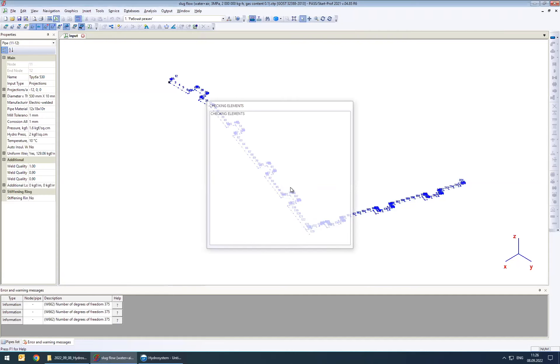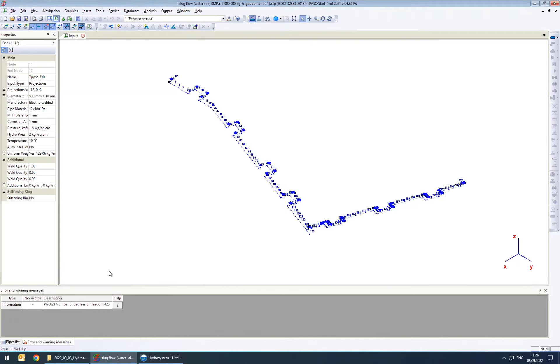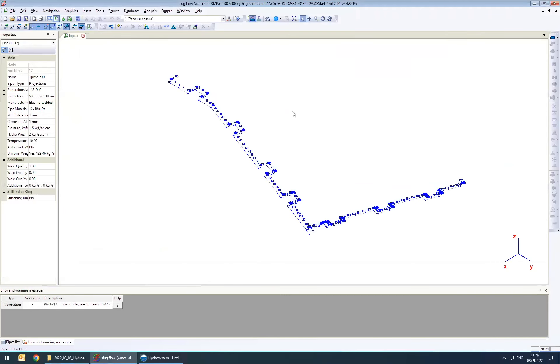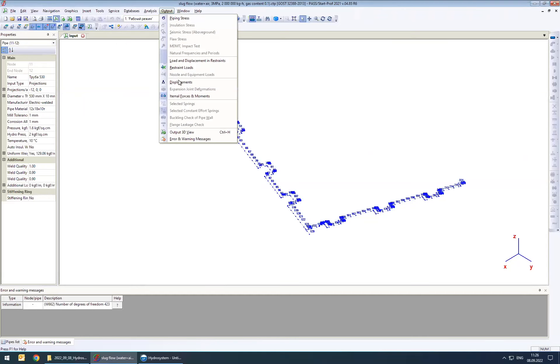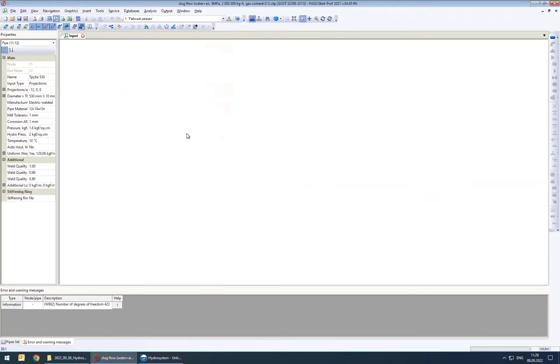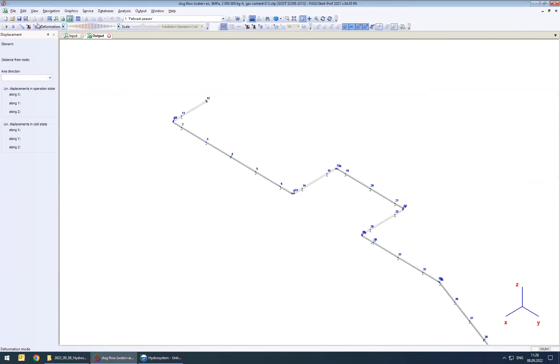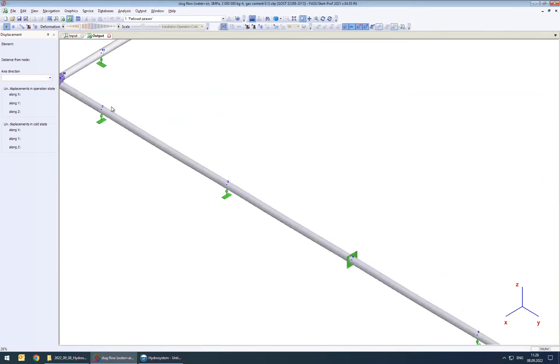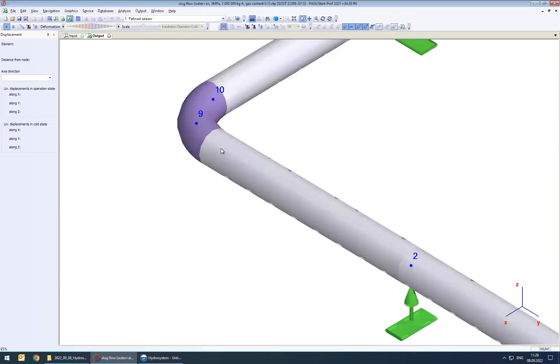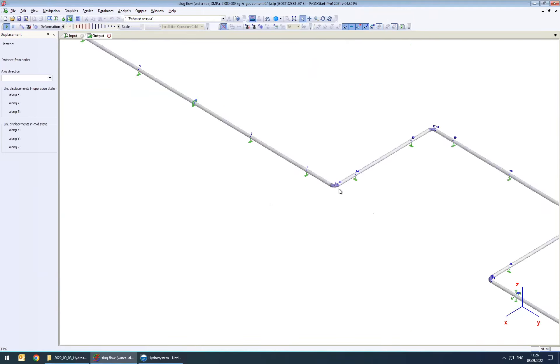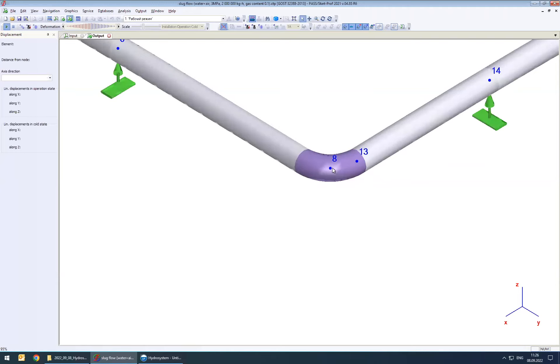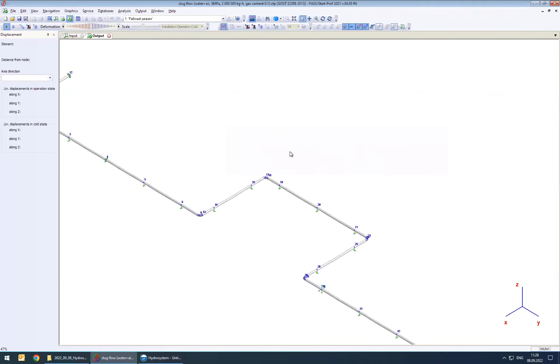Let's perform the calculation. We see that everything is fine — no warnings, no errors. Let's check the movements. In StartPro, you can see how your piping is moving. Looking at the working mode and the nodes, we have very slight movements — the piping system is moving just a little bit, but nothing crucial.